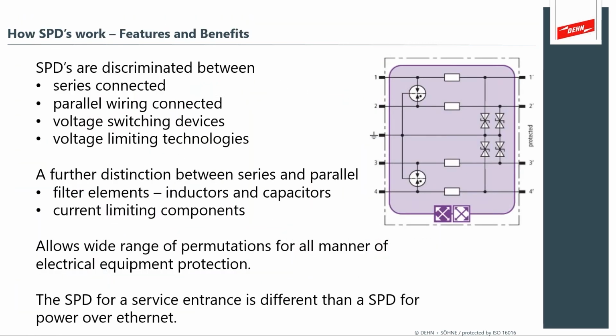So how do SPDs work? What are the features and benefits of an SPD? Well, SPDs basically can be described as series connected or parallel connected, voltage switching or voltage limiting type technologies. There's also a further distinction between series and parallel with filter elements like inductors and capacitors and current limiting components like fuses and breakers. This allows, when combined, a very wide range of permutations so that you can develop surge protection devices specifically for that electrical equipment protection. And you would see this because an SPD for a main service entrance is different than what you would use as an SPD for a power over Ethernet circuit.